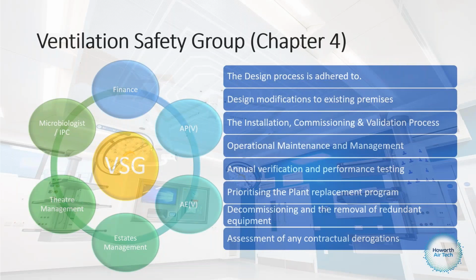Now, the ventilation safety group, like I say, my best bit, my favourite bit. And the reason is because these people should be making sure that everything that comes from contractor to NHS to private healthcare, whoever it is, is designed as fit for purpose, in line with their scope, and that no one's trying to wriggle out of anything contractually along the route. So they need to look at if the design process is adhered to, design modifications to existing premises are undertaken correctly, the installation, commissioning and validation process is carried out and completed, operational maintenance and management, annual verification and performance testing is carried out at the right time each year.